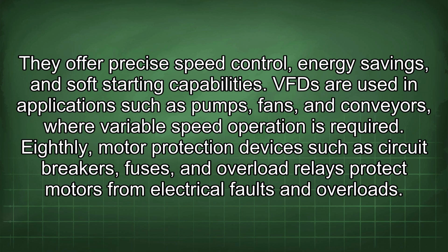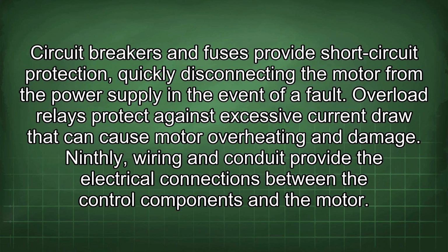Eighthly, motor protection devices such as circuit breakers, fuses, and overload relays protect motors from electrical faults and overloads. Circuit breakers and fuses provide short-circuit protection, quickly disconnecting the motor from the power supply in the event of a fault. Overload relays protect against excessive current draw that can cause motor overheating and damage.